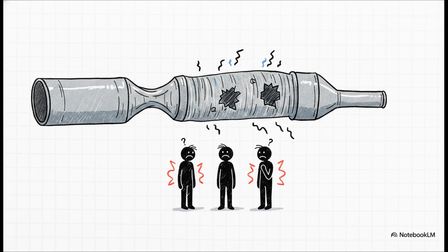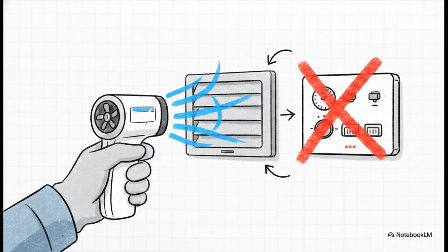You might even just have excessive static pressure, which simply means there's too much air resistance in the pipes for the fan to overcome. So occupants are constantly complaining about uneven temperatures, but the solution definitely isn't just making the air colder. To actually fix this, you can't just glance at the thermostat temperature and guess what's wrong. You really have to investigate the scene.